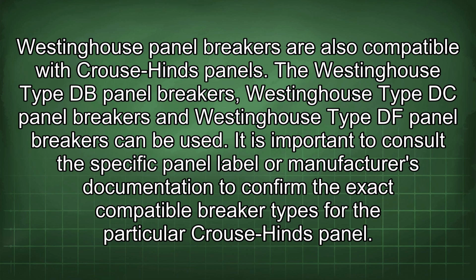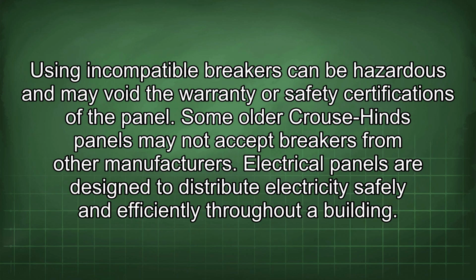It is important to consult the specific panel label or manufacturer's documentation to confirm the exact compatible breaker types for the particular Crouse-Hinds panel. Using incompatible breakers can be hazardous and may void the warranty or safety certifications of the panel. Some older Crouse-Hinds panels may not accept breakers from other manufacturers.